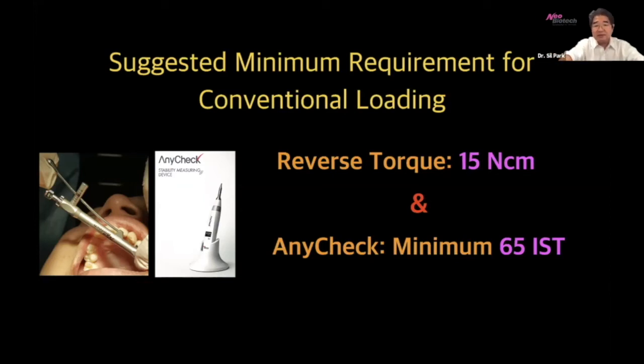And then you place the healing abutment and measure the AnyCheck, and if that number is more than 65 IST, then you are good to go, right?